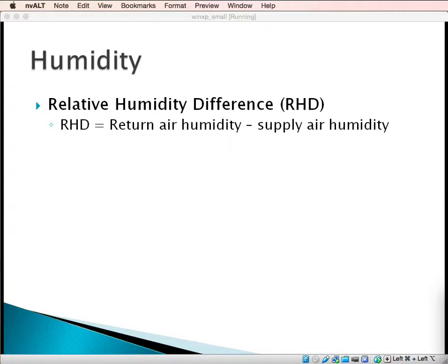Humidity is a measurement of moisture content in the air. Humidity is really bad for computing equipment, so data centers usually try to control humidity. This relative humidity difference (RHD) can be used to find opportunities to reduce energy use if there's actually humidification and dehumidification within the data center.